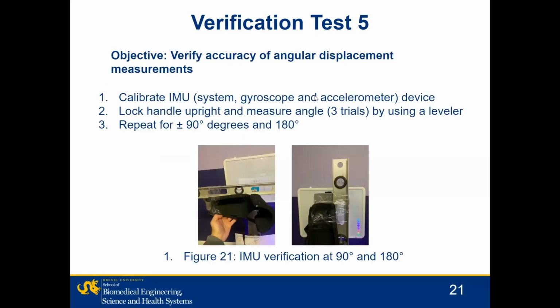For the angular displacement verification test, the IMU, the system, the gyroscope, and the accelerometer are calibrated. Then the handle is locked upright, and this is determined as 0 degrees. The handle is moved to plus or minus 90 degrees, which is right or left, and also to 180, which is when the handle is pointing downward. 3 trials are measured for each angle.